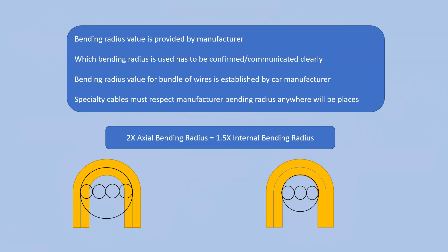You can't calculate it because you don't know what materials were used. Asking how to calculate bending radius is like asking how to calculate the melting temperature of metals — it depends on which metal: aluminum, copper, or steel. You can't calculate the melting temperature; you have to melt it and record it. Similarly, cable manufacturers bend the cable and determine the healthiest bending radius it can take in different environments.